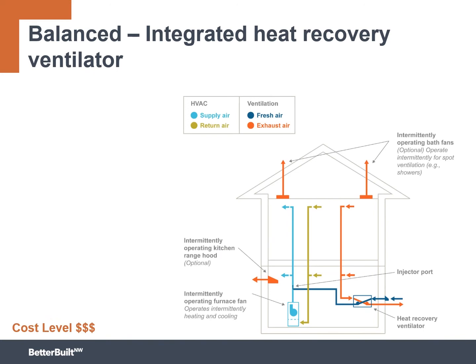So maybe you're saying, well, I don't want to run twice as much ductwork because I do have a central air handler. Again, maybe I have a gas furnace with an air conditioner, or maybe I have a central heat pump. Well, there is an option to integrate a heat recovery ventilator into that central air handler. And this sometimes combines both the best and the most challenging components of the other options. So in this case, the HRV or ERV is going to be ducted directly into the central ducting system for your central air handler. So this might reduce the amount of new ductwork needed and should ensure great distribution, right? Because your central air handler is already moving air to all the rooms.